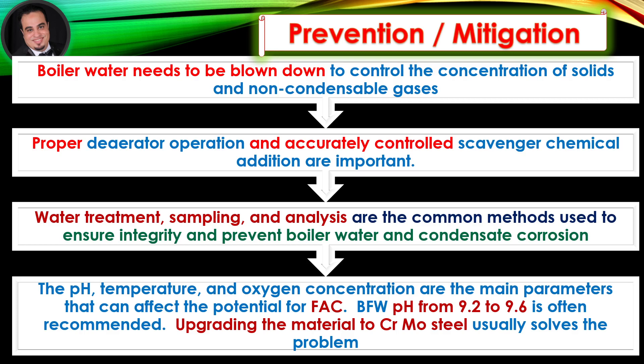Water treatment, sampling, and analysis are the common methods used to ensure integrity and prevent boiler water and condensate corrosion. The pH, temperature, and oxygen concentration are the main parameters that can affect the potential for flow accelerated corrosion. Boiler feed water pH from 9.2 to 9.6 is often recommended. Upgrading the material to chromium molybdenum steel usually solves the problem.